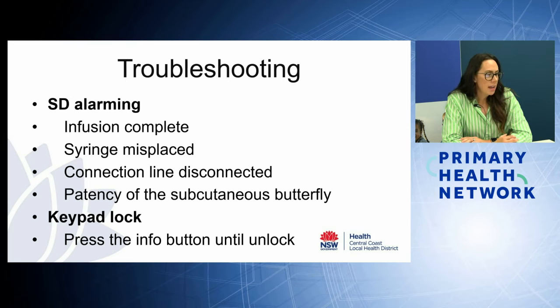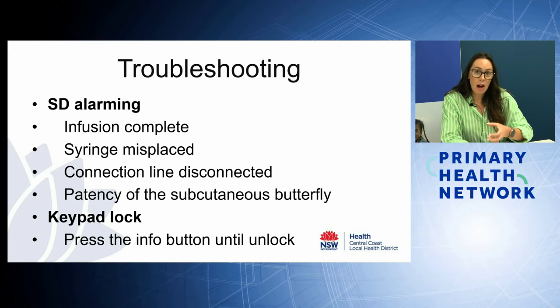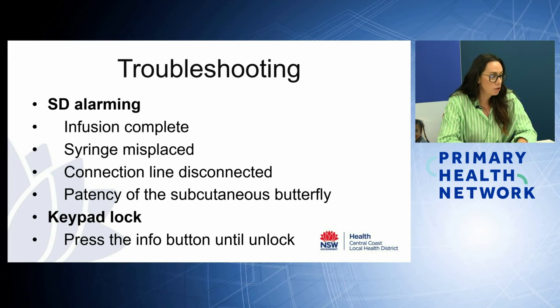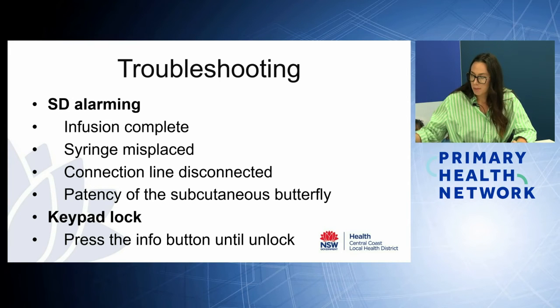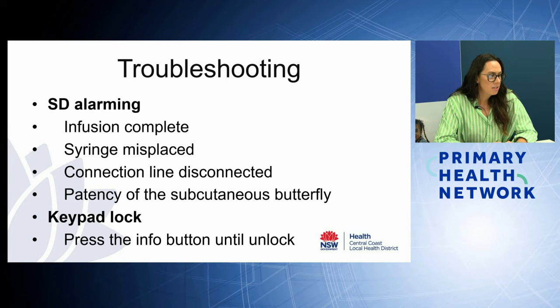With troubleshooting, again, if the syringe driver is alarming, there can be numerous reasons for that. The main thing is that it's complete, so the actual infusion has run through its 24 hours. It will start to alarm, and it will also alarm when we're very close to the end of the program. So ensure that that is the case. Sometimes the syringe has actually misplaced and it's moved off-site, so it will actually alarm to let you know that. If the line has been disconnected, either from the patient or from the actual syringe itself, it can detect that, and that the patency of the butterfly is actually flowing.